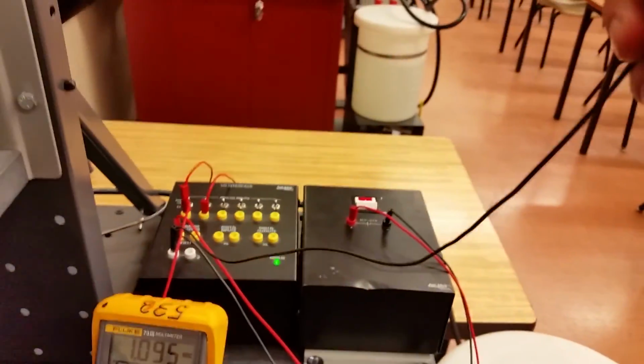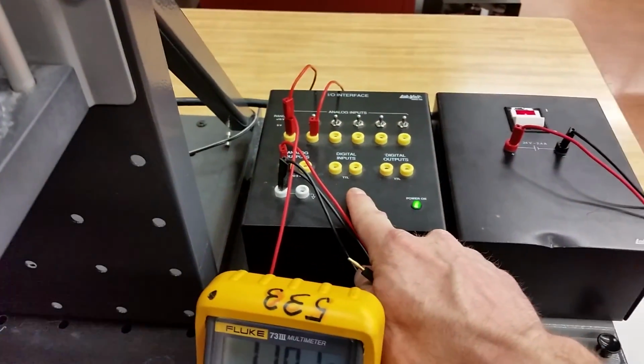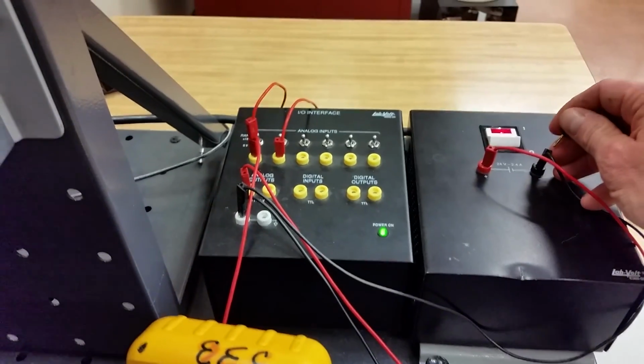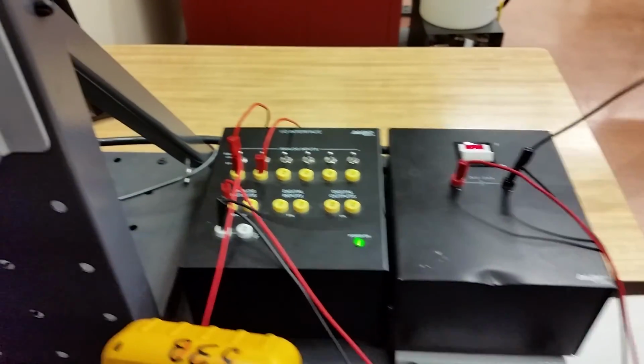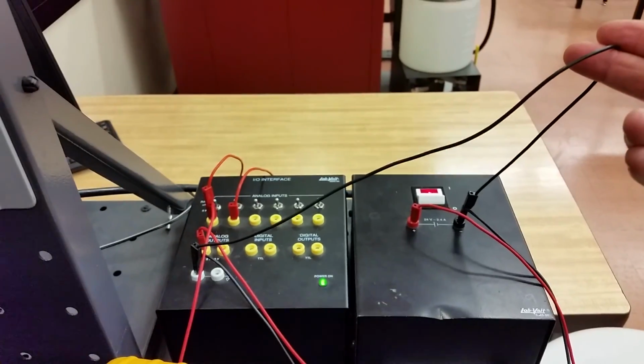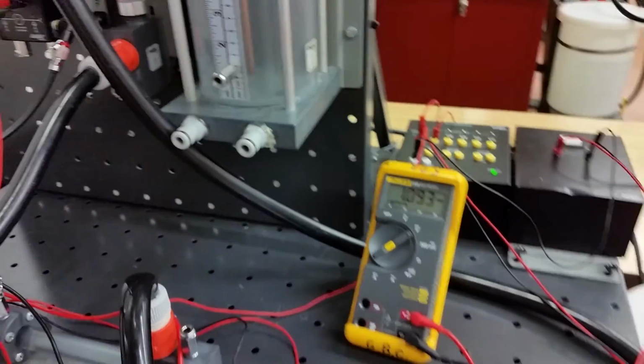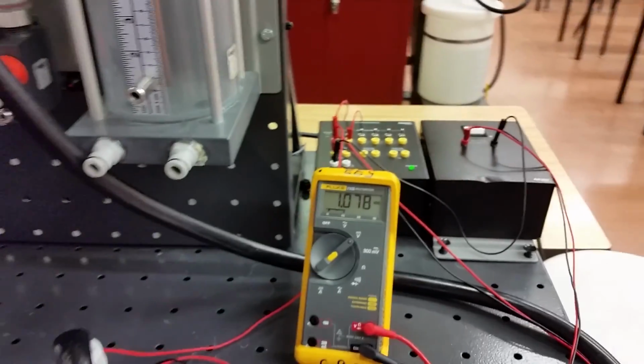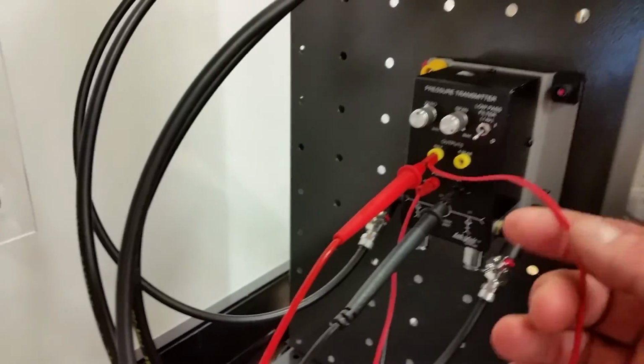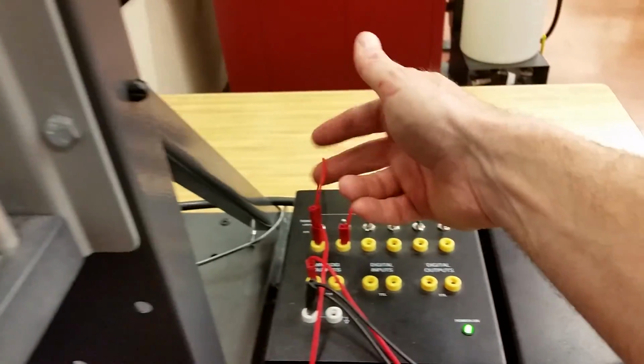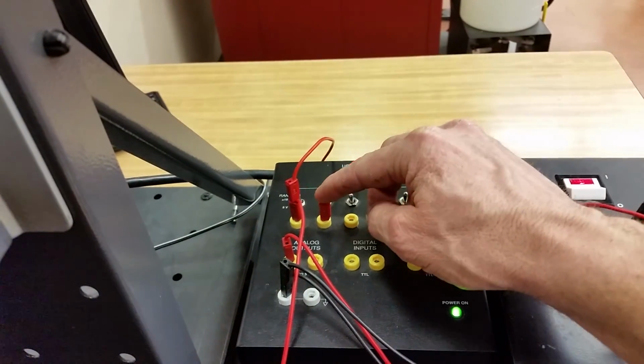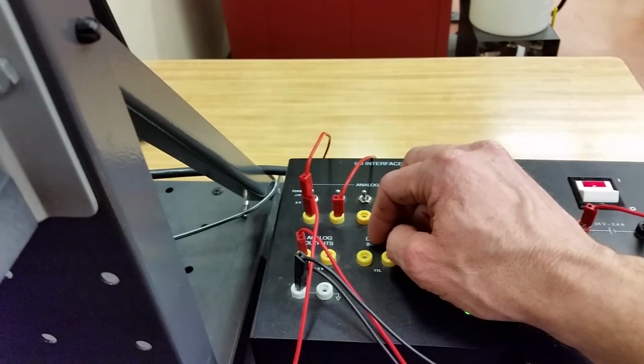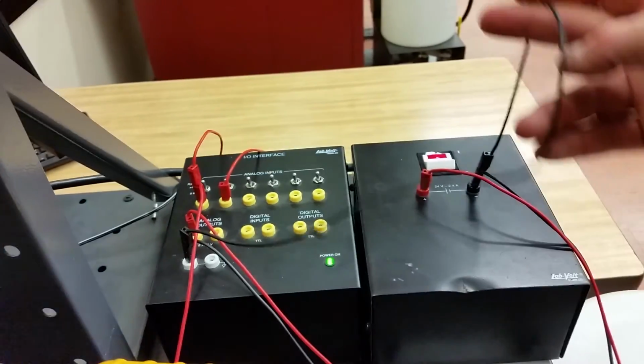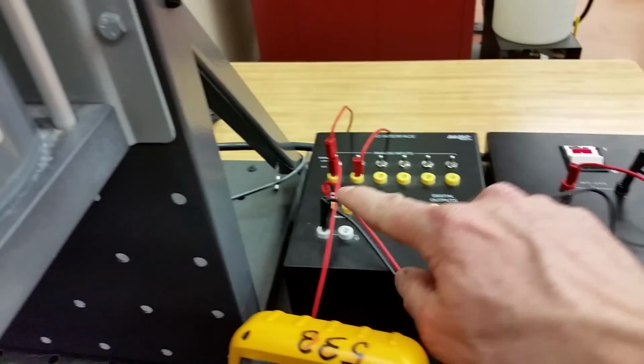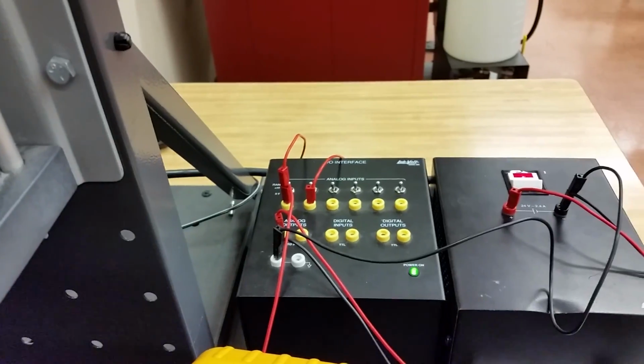So this wire right here is crucial as well. Between the I/O interface and the 24 volts, they both need to see the same reference for the common. Otherwise, what you see on the screen is not going to reflect what's happening out in the field. One more time: one wire from the 0 to 5 into the analog input, jump it over to the next one if you want to have two things on the screen, and then refer the 24 volt power supply to the same common, and you're ready to rock and roll.